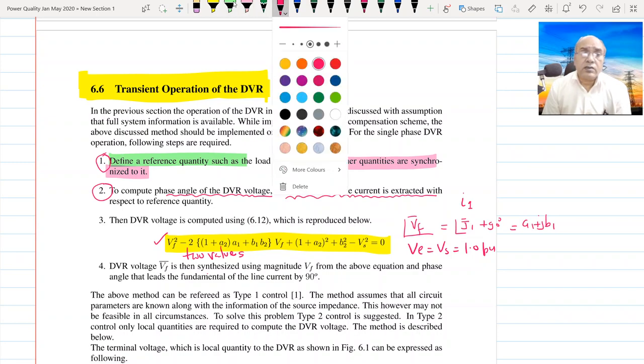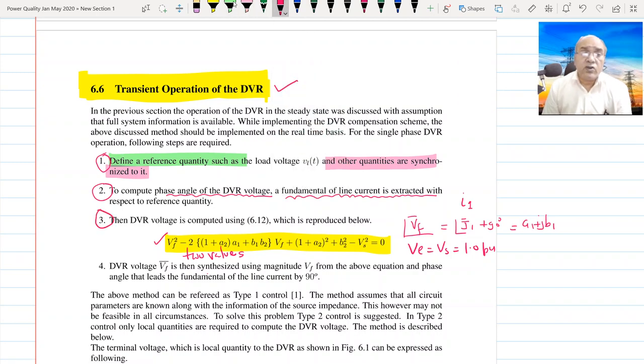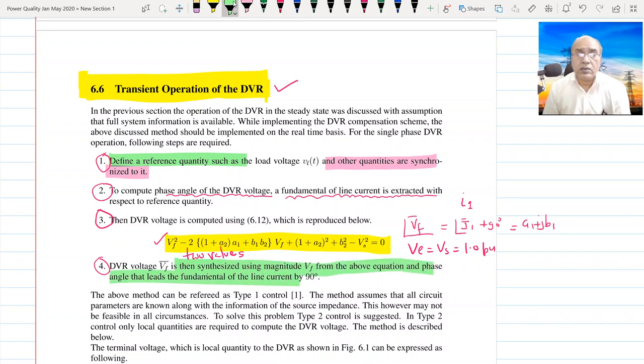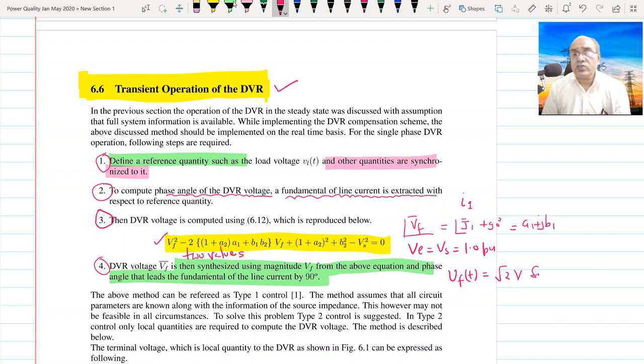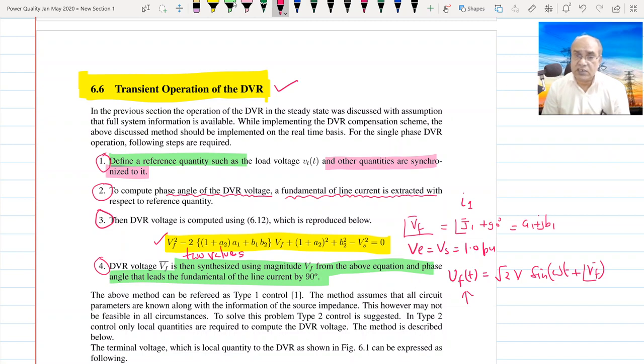We take the least value because it is more optimum to realize the DVR power. The fourth step is to construct the voltage in the time domain and synthesize it with the help of the power circuit. We construct VF(t) = √2 × V × sin(ωt + angle of VF), and once we know this, we track it using a filter or voltage source inverter topology.